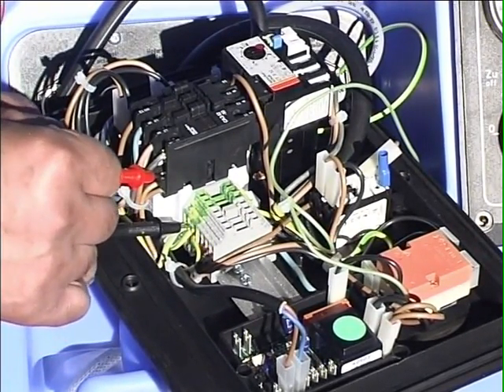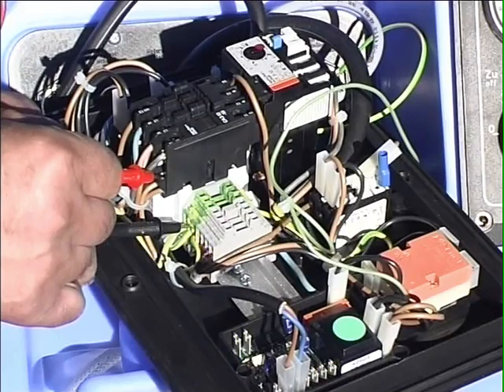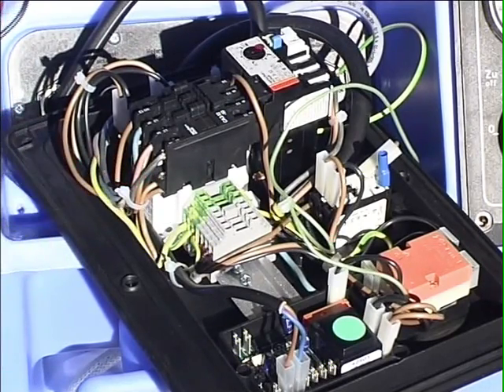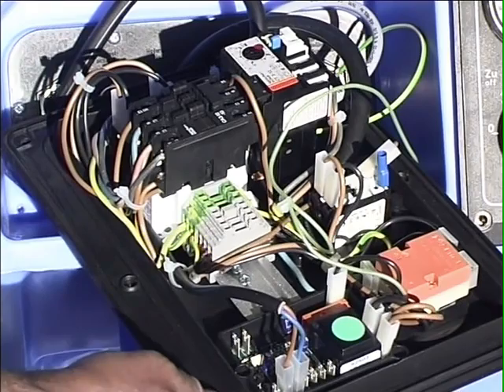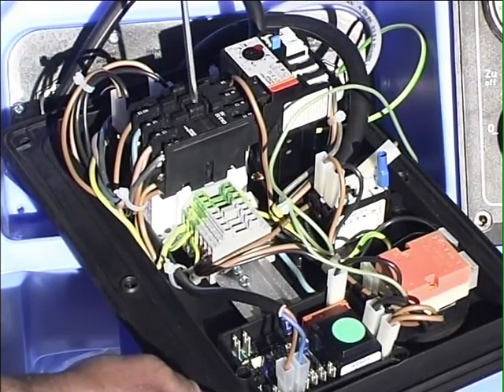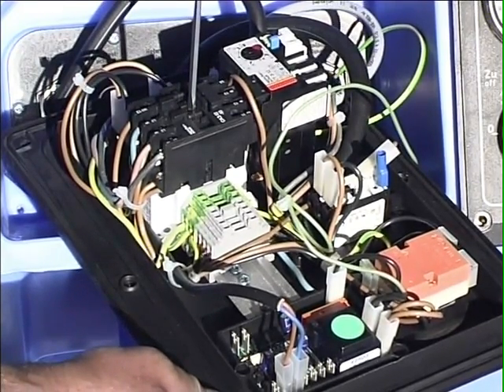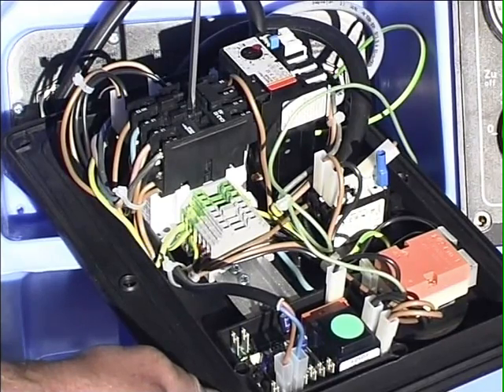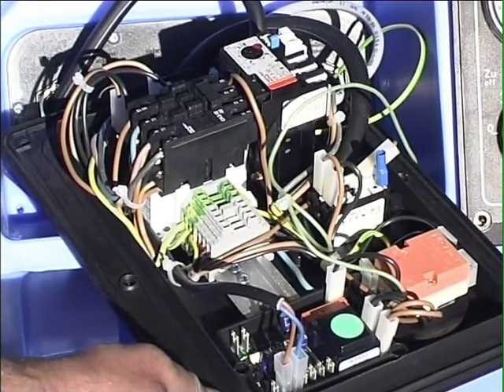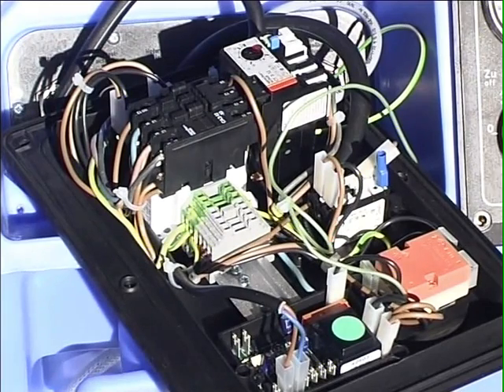If there is voltage on the protective coil, but the machine does not start, you can use a screwdriver to mechanically move the contactor and start the machine for test purposes. If the machine now starts, there are 2 possibilities. Check the cable connections and contacts. If the contactor is defective, replace it.